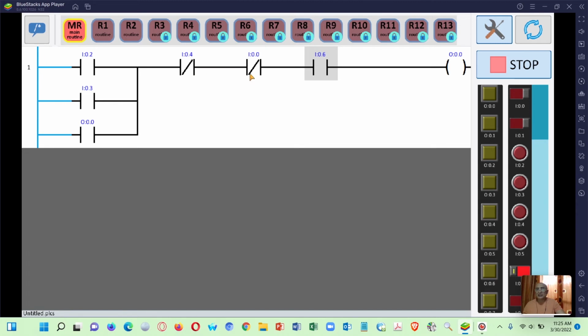These two contacts for the stop button are also already true. So if I press the start button, we have our latching contact, and the motor is now latched. Then I can push the stop on the first location, push the start on the second location, and push the stop on the second location.